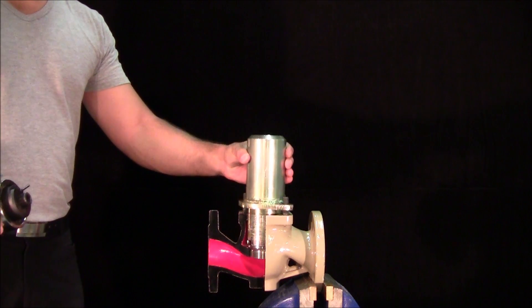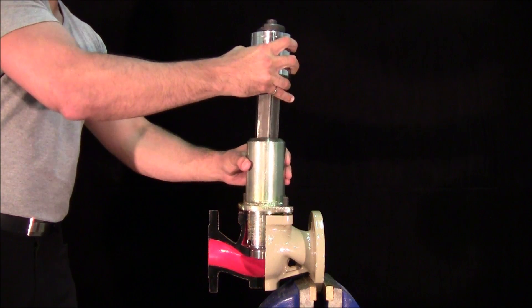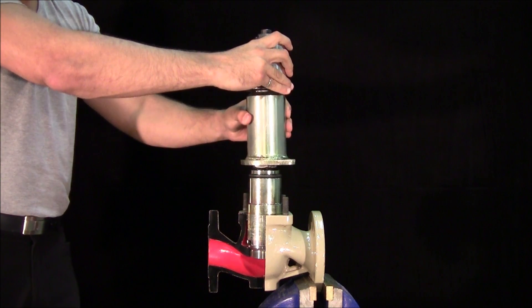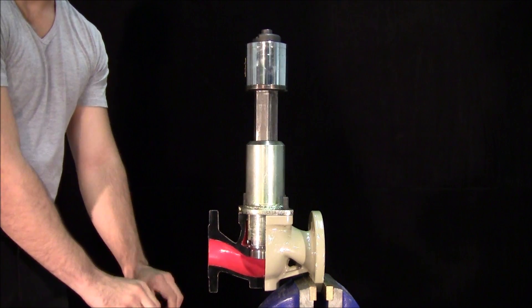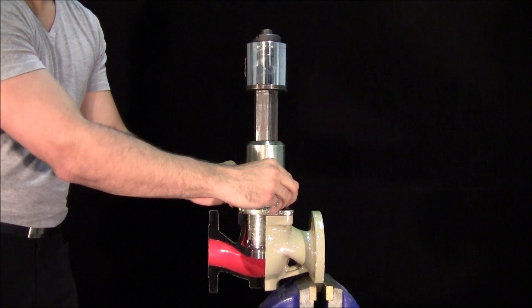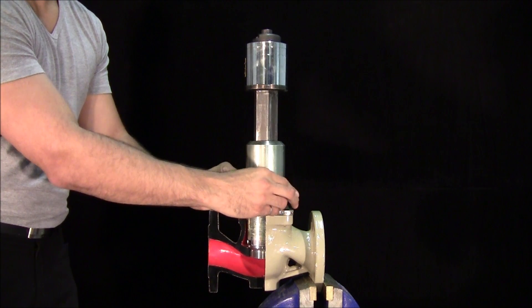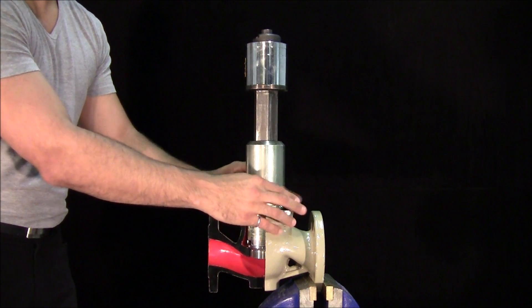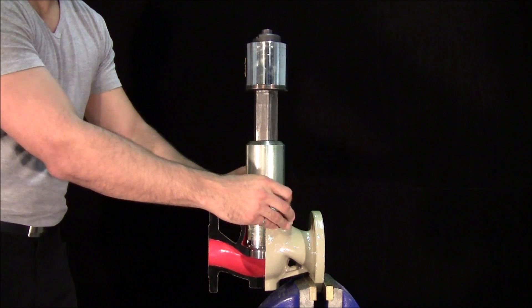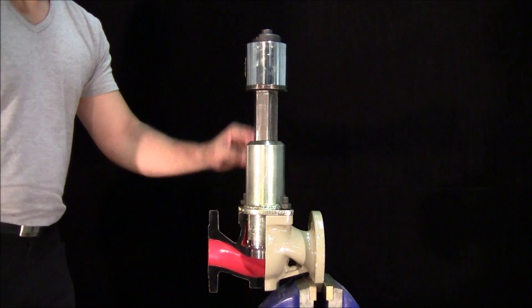Now, the seat tool, support flange and torque multiplier can be used to tighten the seat to the required torque specification. Install two nuts to hold the tools firmly to the valve body before using a torque wrench.